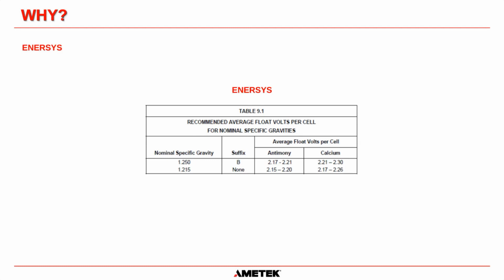But they're saying if it is a 1.25 specific gravity cell that has an antimony plate grid, then the float voltage should be anywhere between 2.17 and 2.21. So in that circumstance, it should be about 2.19 volts per cell. And if it was a 1.215 specific gravity, it should be between 2.15 and 2.20 for the antimony cell, which would be about 2.17 volts per cell. And then for the calcium cell, which is by far the most common, a 1.25 specific gravity is between 2.21 and 2.30, which is where we get 2.25 from.